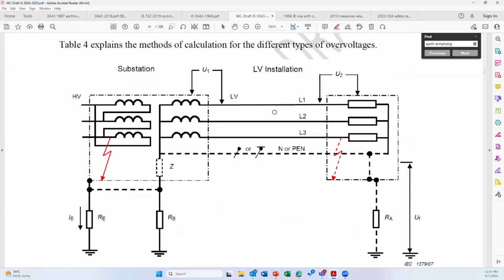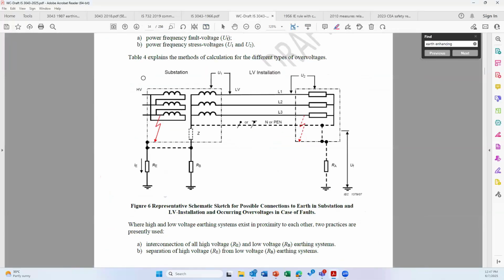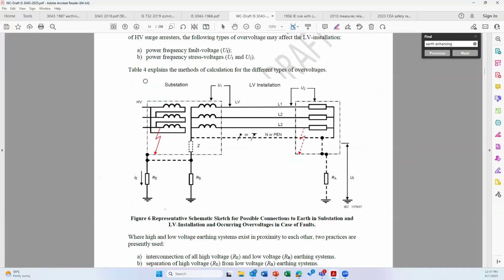More importantly, by mistake we are assuming values for duration and the fault current. We have to assign the fault current. For duration, the CEA Grid Standard Regulation 2010 has clearly provided the maximum fault clearance duration. For example, for 220 and 132 kV, it should not exceed 160 milliseconds. For 400 and 765 kV, it should not exceed 100. But what we are seeing in all the calculations is 0.5 second. So in important areas, we are assuming things and going against the standards. Here, in this standard, everything is clearly given.